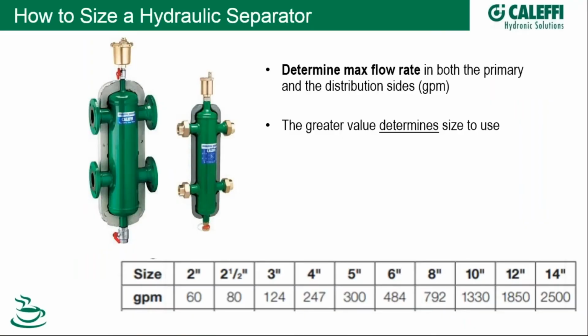So a question came in before the webinar: how do you size a hydraulic separator? Well, it's pretty straightforward, and here is the criteria. You determine your max flow rate, otherwise known as your design flow rate, in the primary side of your system, and then also separately in your secondary side, your distribution side. And the greater value of the two determines which size separator to use in your application.